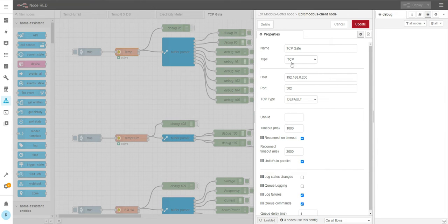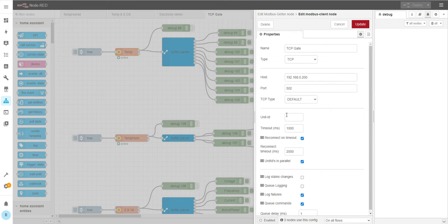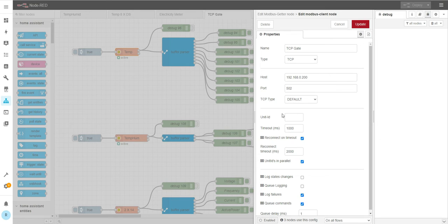Okay, so type TCP, address of the gateway, port, and unit ID. Best to leave zero because you may use this config settings for various devices. So basically, you will put that unit ID on your separate nodes.